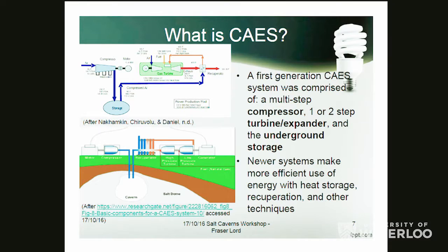When you put these aspects together, you get images like the one in the bottom left — the turbomachinery and the cavern together. You've got a compressor, typically in multiple stages for efficiency, cavern storage, and two to three stages of expansion power, again for efficiency. Newer CAES systems involve a recuperator and other techniques to improve efficiency. Newer ideas, like appending compressed air onto a traditional natural gas turbine, are developing as well. The two existing CAES facilities have specially designed expanders just for their facilities.